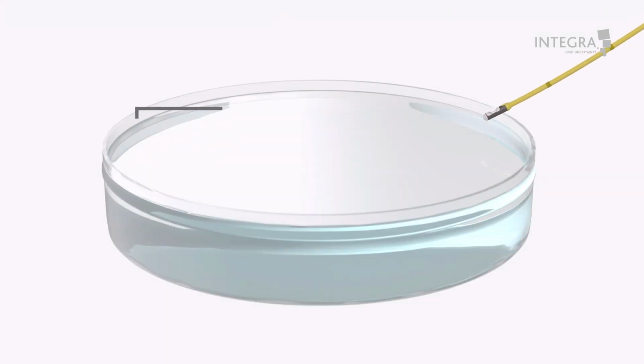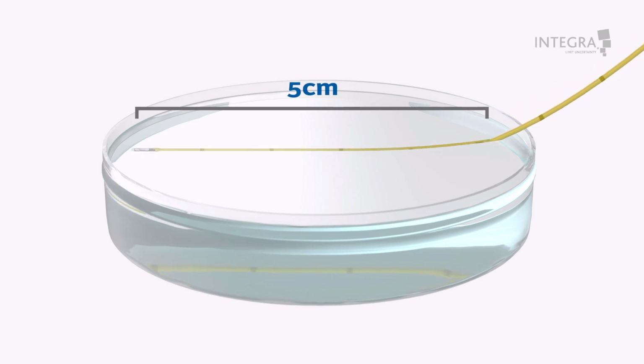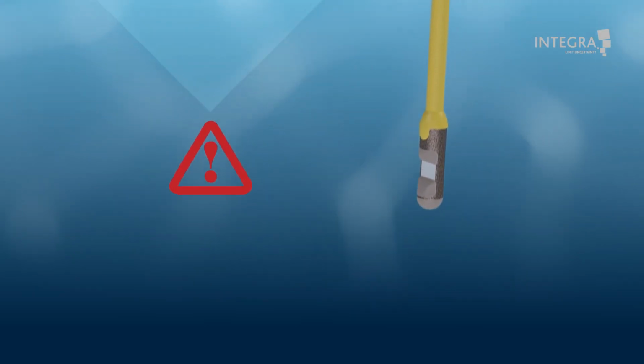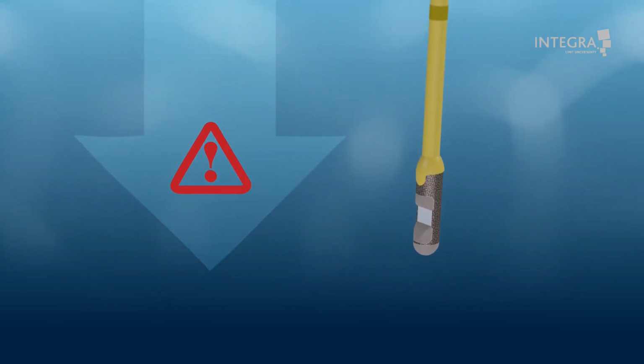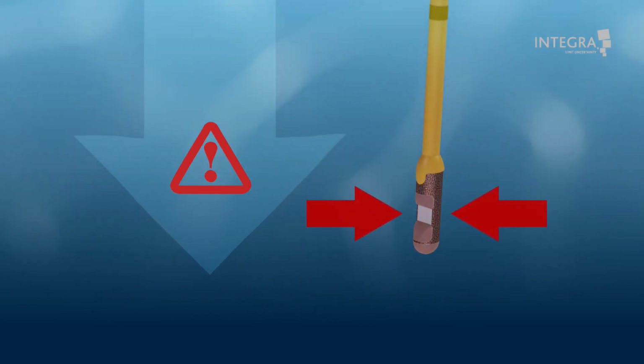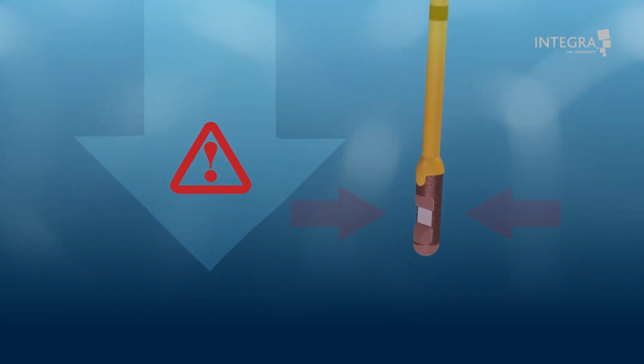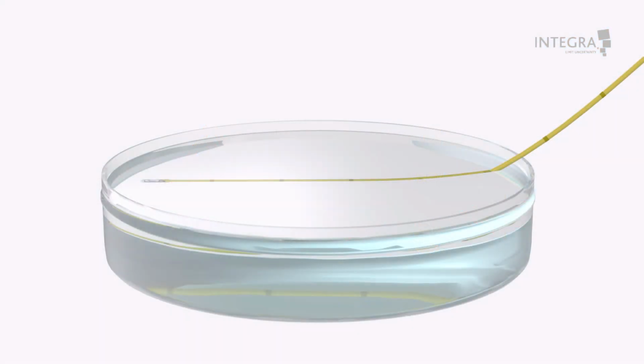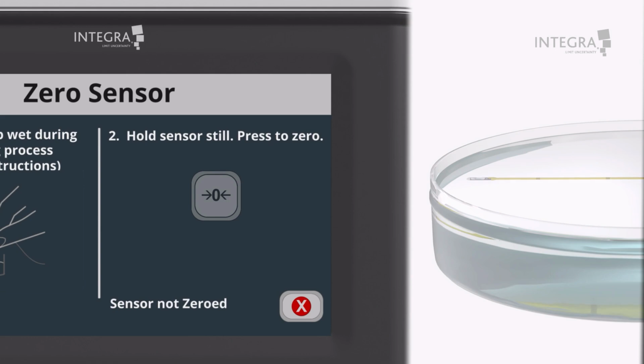Using sterile technique, lay at least a 5 cm section of the sensor horizontally just under the surface of the sterile water or sterile saline. Do not submerge the tip of the ICP sensor vertically in a deep pool of sterile water or sterile saline. Doing this will impose a hydrostatic pressure on the ICP sensor diaphragm that is higher than atmospheric pressure, resulting in an inaccurate 0 reference. Hold the sensor still without applying any external pressure to the tip apart from the sterile saline. If the device senses the sensor is moving, a 0 button will not be available.